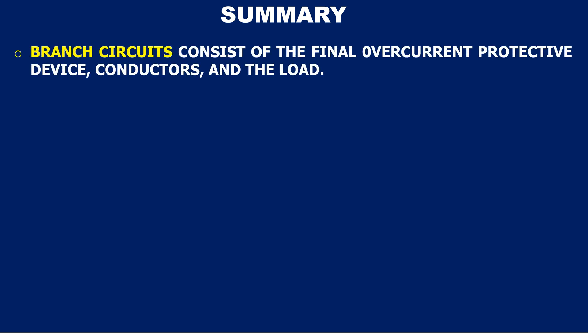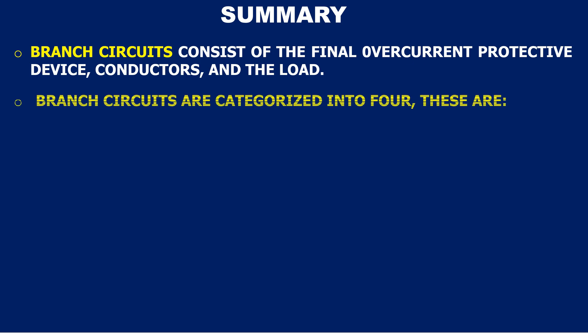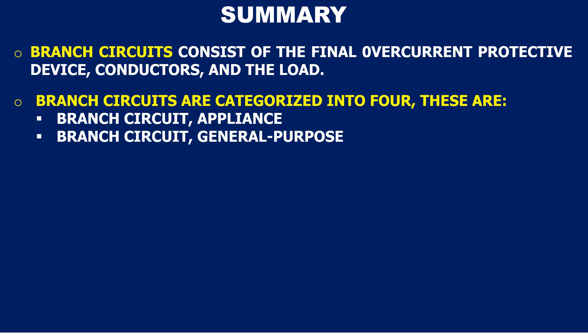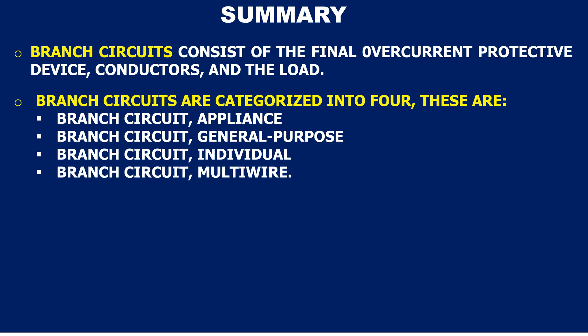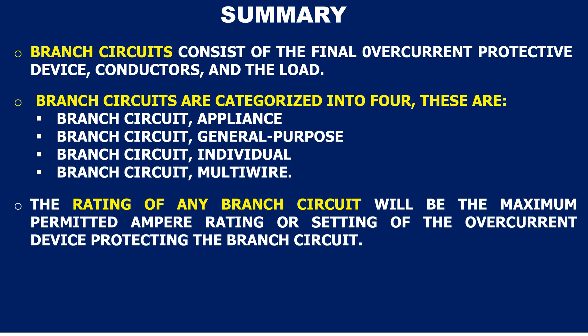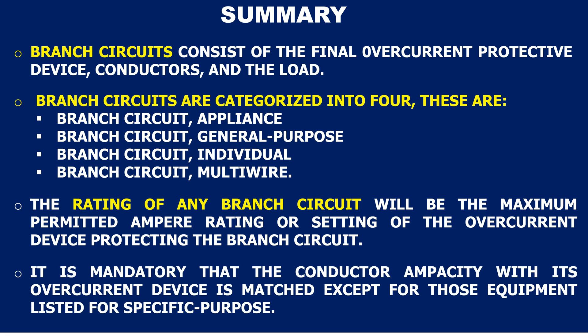To summarize our topic: branch circuits consist of the final overcurrent protective device, conductors, and the load. Branch circuits are categorized into four: 1. Branch circuit appliance. 2. Branch circuit general purpose. 3. Branch circuit individual. 4. Branch circuit multi-wire. The rating of any branch circuit will be the maximum permitted ampere rating or setting of the overcurrent device protecting the branch circuit. It is mandatory that the conductor ampacity with its overcurrent device is matched.